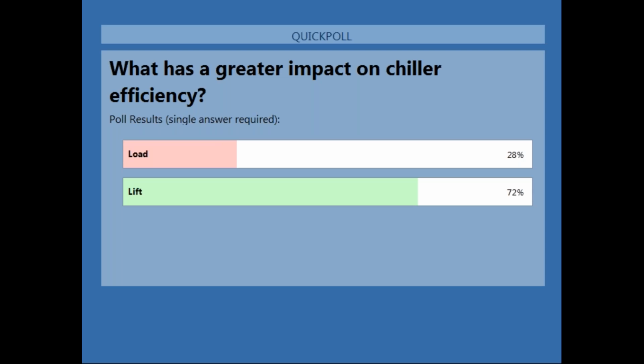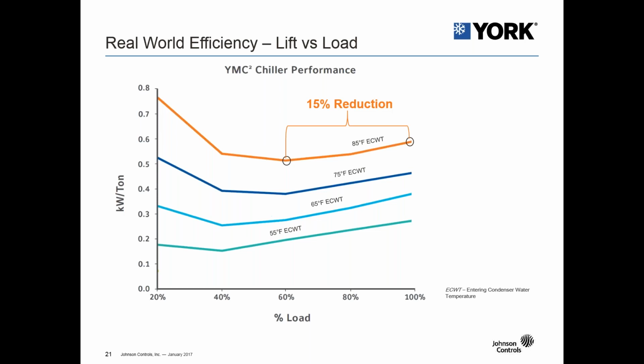Okay, so taking a look at the results, we have 28% as load and 72% as lift. So the correct answer is lift, and we'll go on to walk everyone through this. So when we look at real-world efficiency, lift versus load, on the left-hand side you'll see kW per ton, and across the x-axis you'll see percent load of the chiller going from 20% up to 100%.